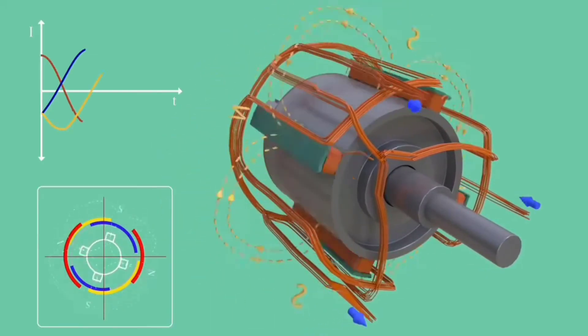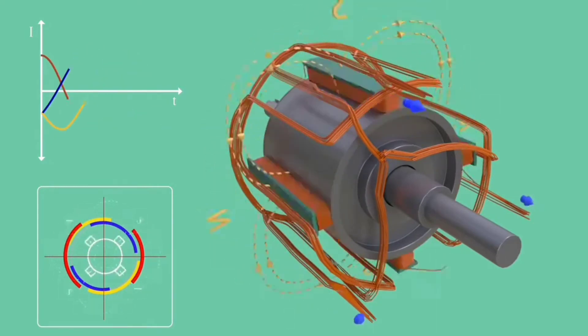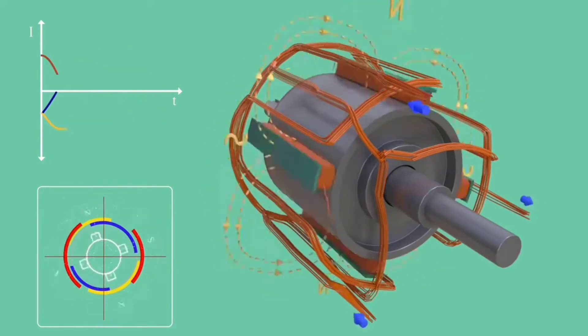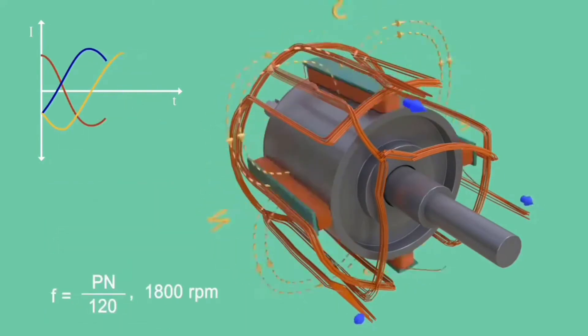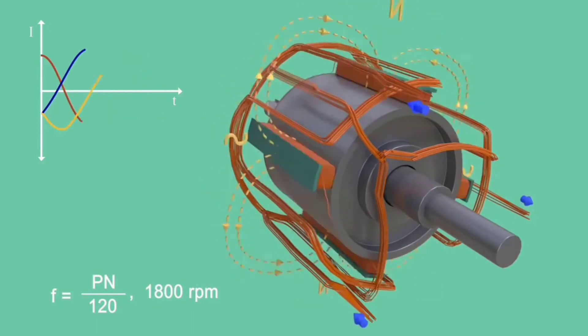It is clear from the equation above that in order to produce 60 Hz electricity a four pole rotor should run at a speed of 1800 RPM. Such huge RPM will induce a tremendous centrifugal force on poles of the rotor and it may fail mechanically over time.